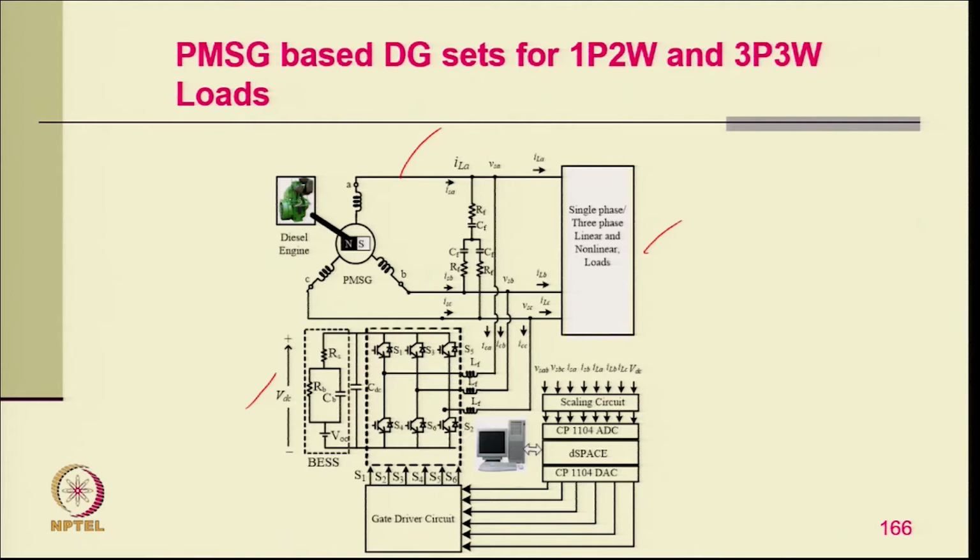utilization in the diesel DG set, because the DG set has to be operated between 80 to 100% load. So, if the load is less than 80%, the battery has to be charged with extra power. However, this battery can give extra power when the load is more than the capacity of the permanent magnet synchronous generator and DG set. That is the benefit. Moreover, during dynamic load conditions, when you have an inrush current of the motor load, the battery can provide instant energy.